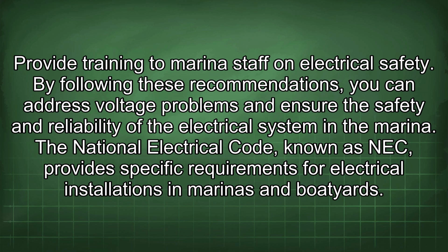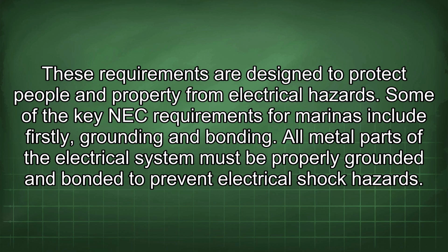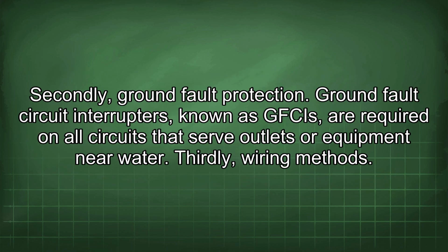The National Electrical Code, known as NEC, provides specific requirements for electrical installations in marinas and boatyards. These requirements are designed to protect people and property from electrical hazards. Some of the key NEC requirements for marinas include firstly, grounding and bonding. All metal parts of the electrical system must be properly grounded and bonded to prevent electrical shock hazards. Secondly, ground fault protection. Ground fault circuit interrupters, known as GFCIs, are required on all circuits that serve outlets or equipment near water. Thirdly, wiring methods.